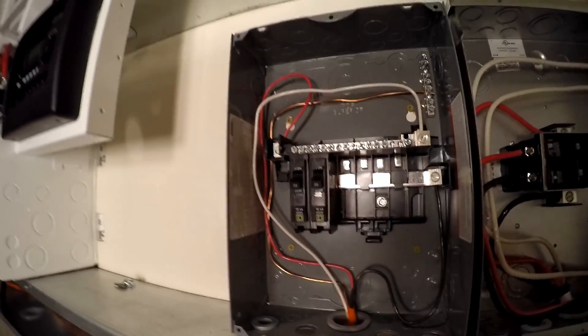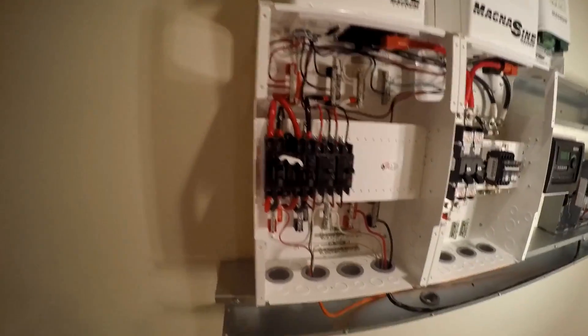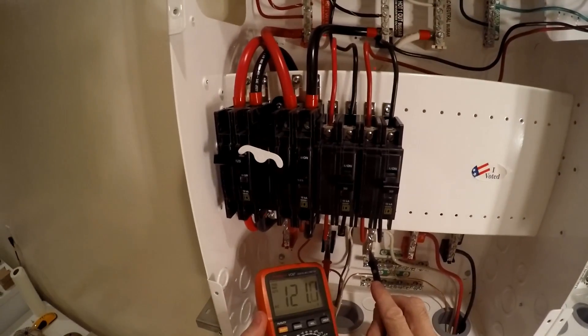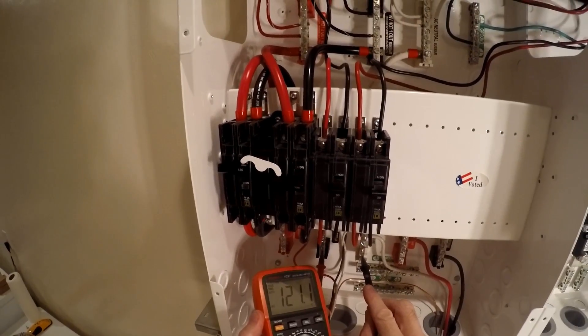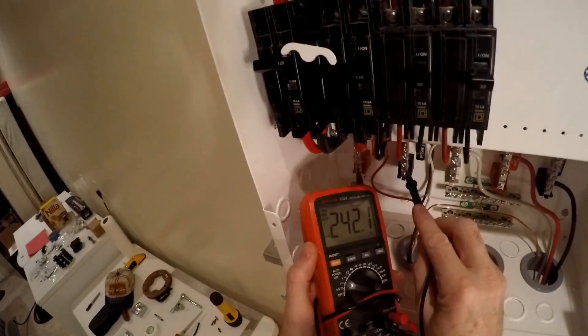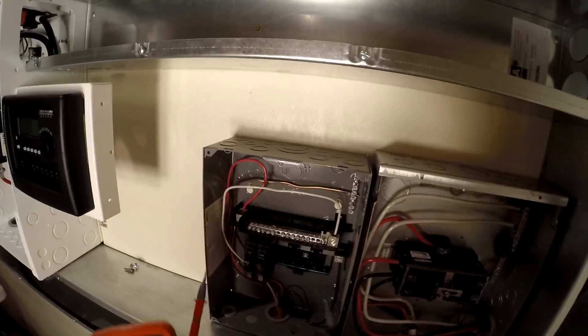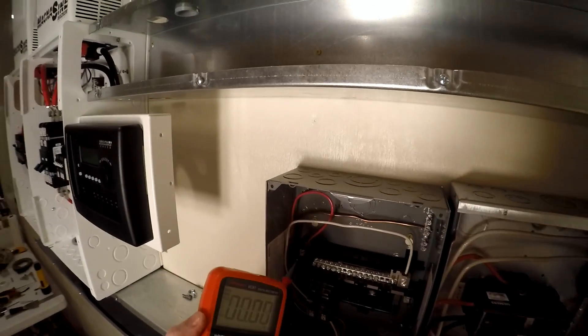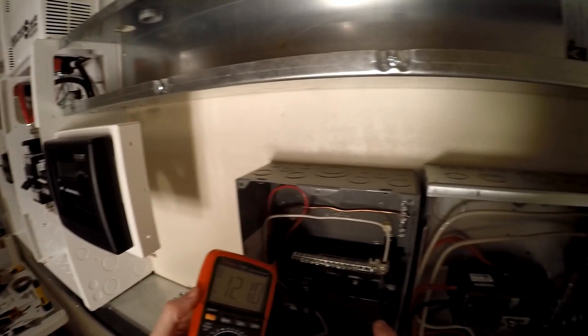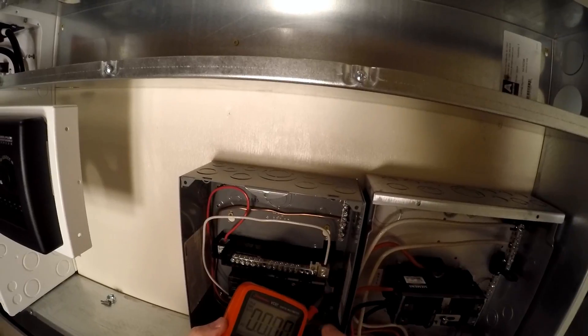I've got a couple of breakers in here so I'm going to turn this on and see what I get. That's half of it, 120. 242, you can see that. And that should take me right over to here, which should also be 240. And there it is, 240. 120, and 120.